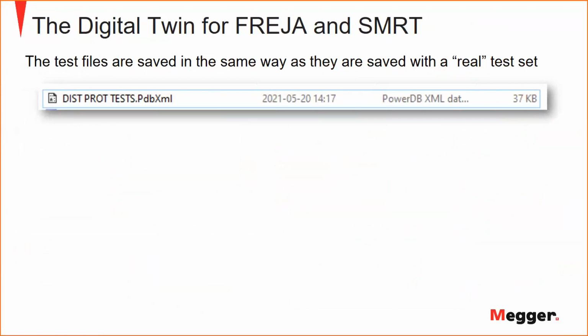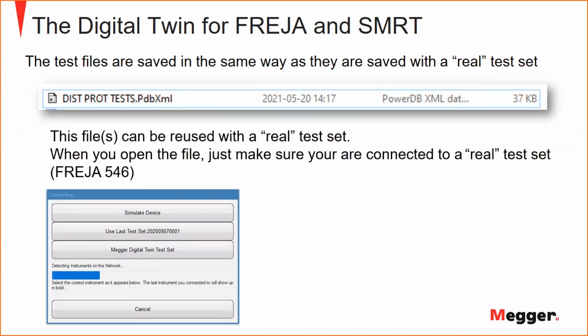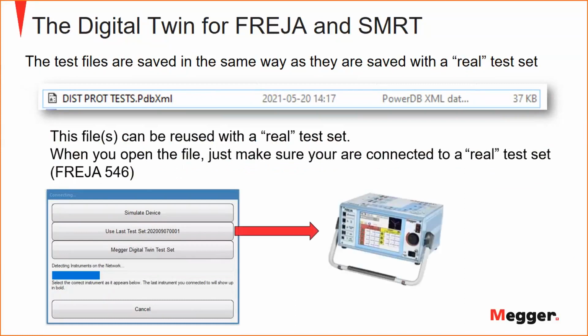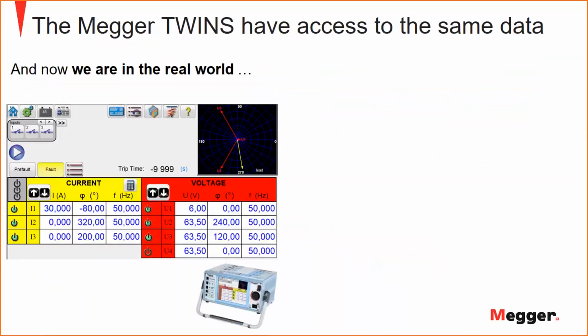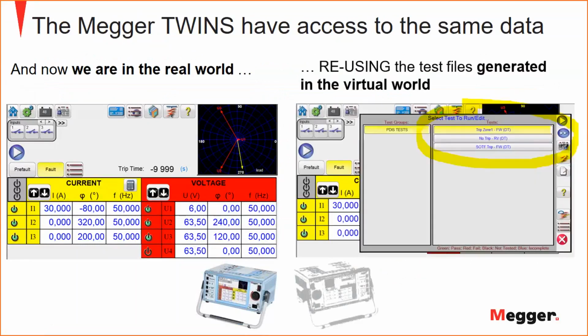The test files are saved in the same way as they are saved with the real test set. The files can be reused, the same file can be used with the real test set. When you open the file, just make sure you connect, of course, not to the digital twin, but to the real test set. So now, when we connect to the real test set, we are in the real world, reusing the files generated in the virtual world. The fact that we are using a COMTRADE to pass data between our digital twin and the real digital twin is just the decision of interface. But we are using the files that have been generated in the virtual world.